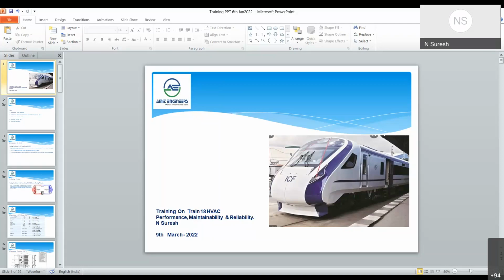The fresh air which comes from outside, as well as the recirculated air, is filtered through two filters, the fresh air filter and the mixed air filter. So the air supplied through the coaches is filtered. This system is a vapor compression system, the basic fundamental system in any refrigeration. The process is compression, condensation, and evaporation. This is how the complete cycle works.